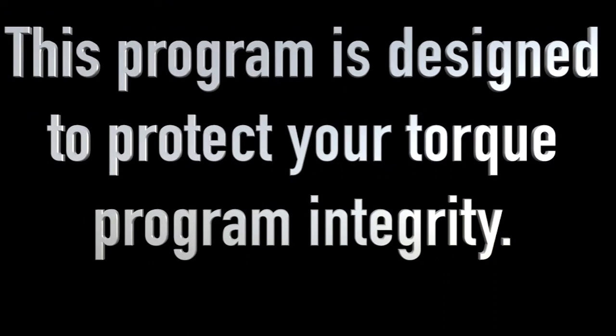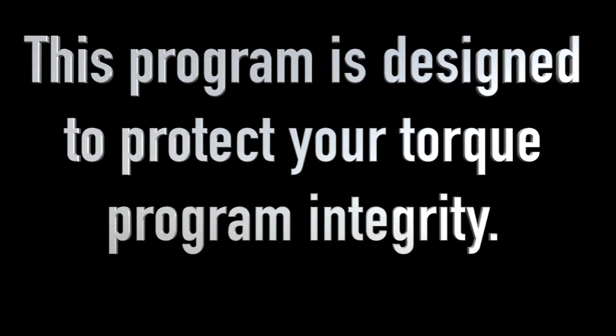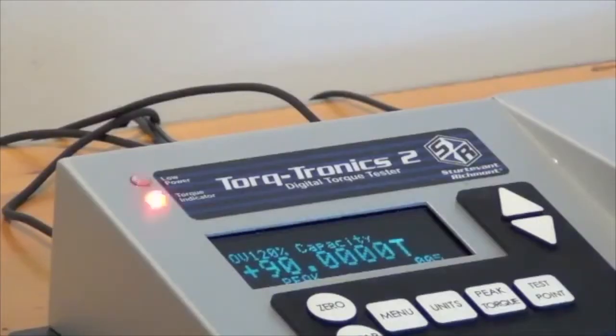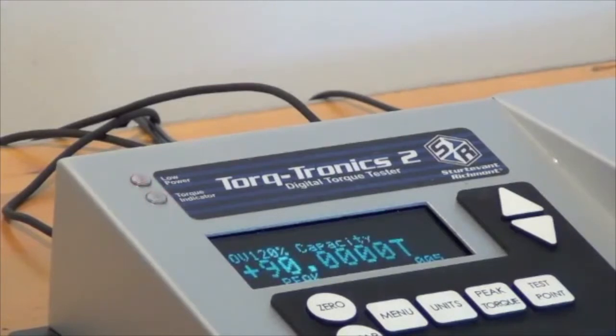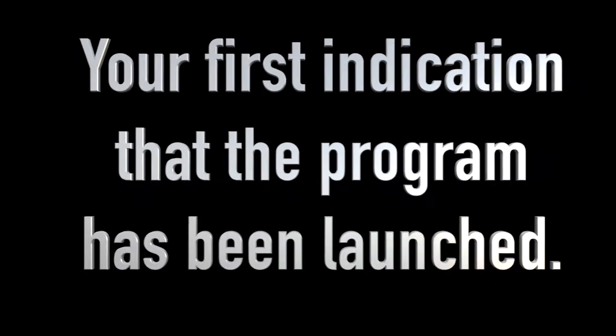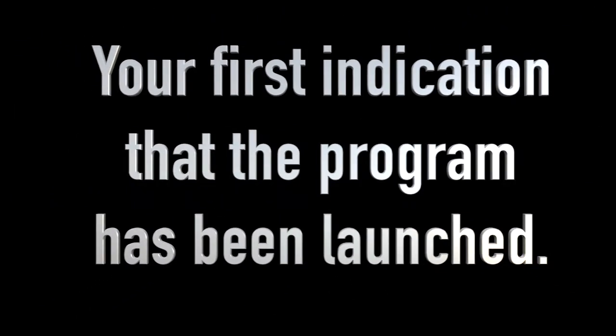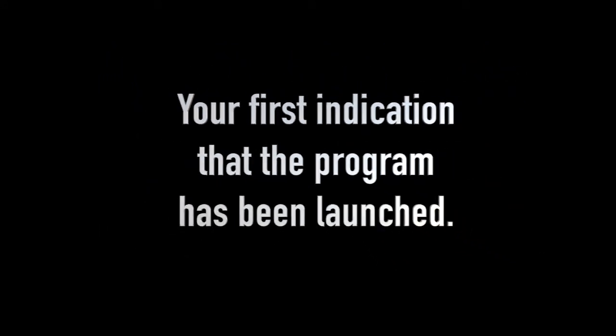We've added this program to your tester as a way to protect your torque program integrity. You'll notice the lower LED on the left-hand side of the tester display constantly flashes. That way you'll know Failsafe Engineering has been initiated.